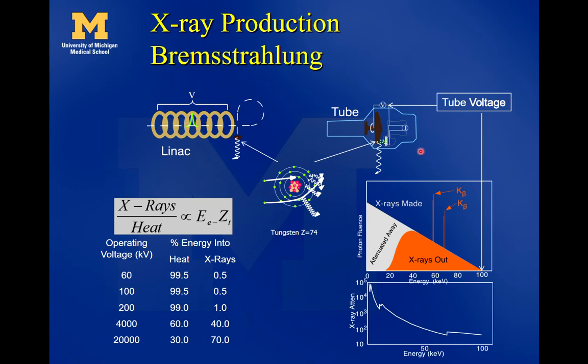Contrast that with an x-ray tube, which is used these days for CT scanning and kV imaging on our linacs. Here we have a tungsten filament with its current source, a voltage across the x-ray tube, and the electrons jump from cathode to anode, collide, and x-rays come out. So in the linac, x-rays are produced when the electron beam hits a target. In the tube, electrons jump the voltage gap and produce x-rays coming out the other way.